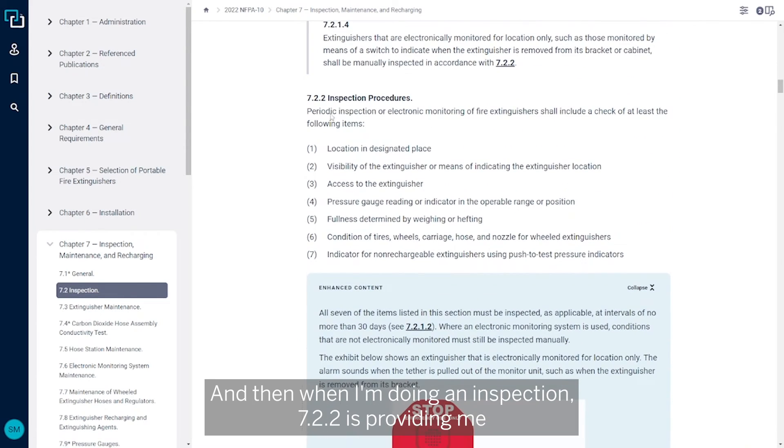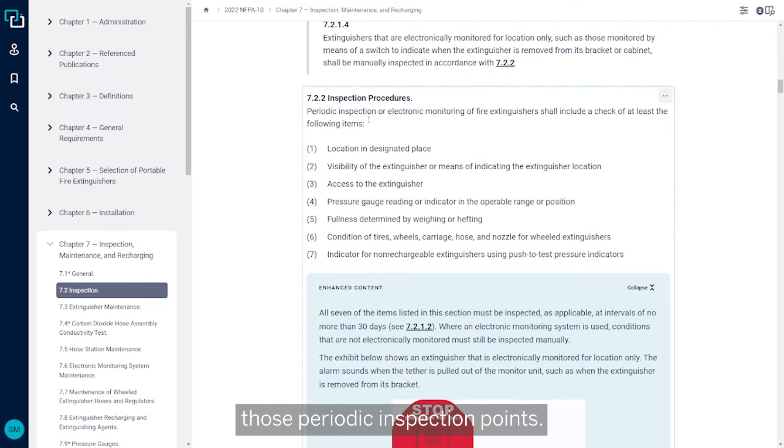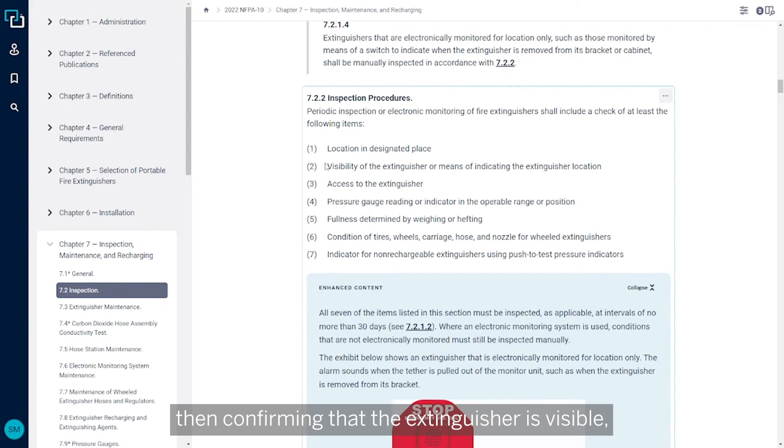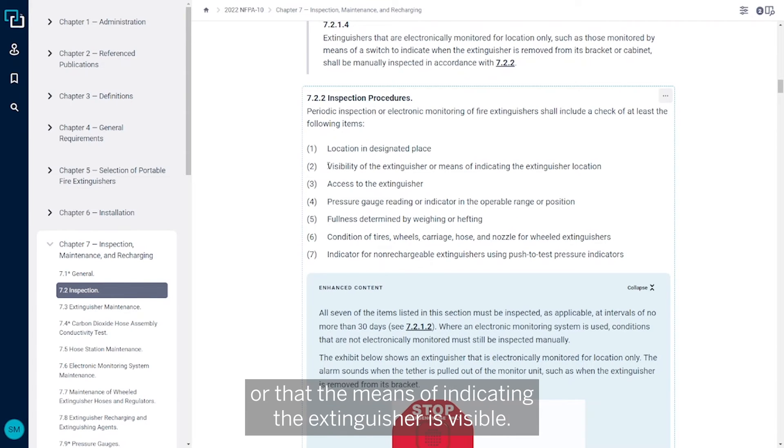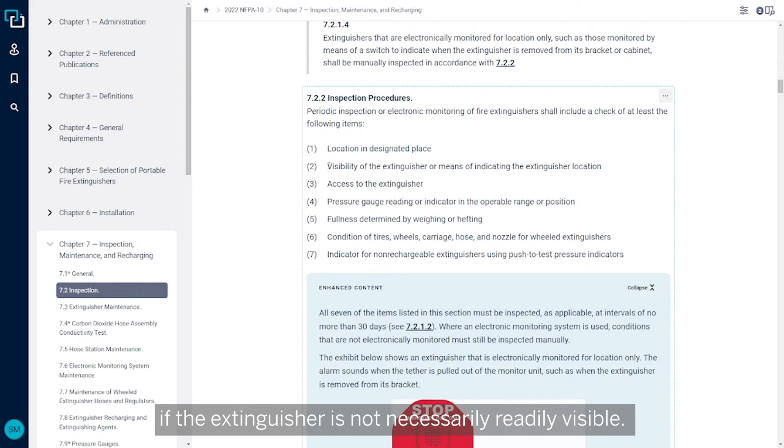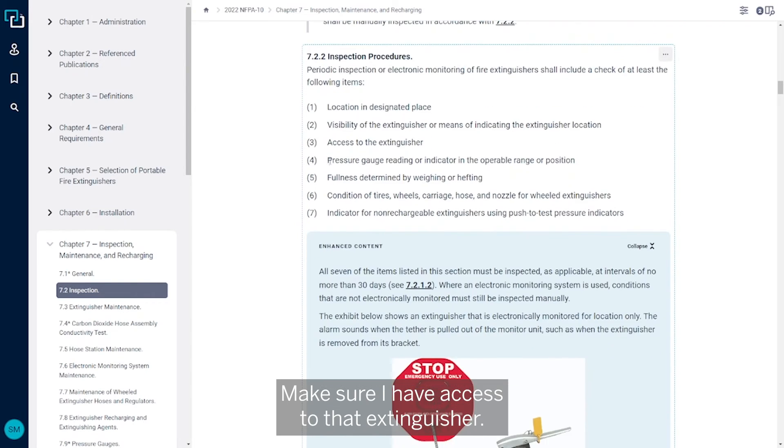And then when I'm doing an inspection, 7.2.2 is providing me those periodic inspection points. The first one being confirming that it's in its designated place, then confirming that the extinguisher is visible or that the means of indicating the extinguisher is visible. So maybe the sign is visible if the extinguisher is not necessarily readily visible. Make sure I have access to that extinguisher.